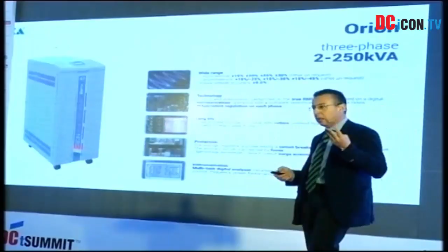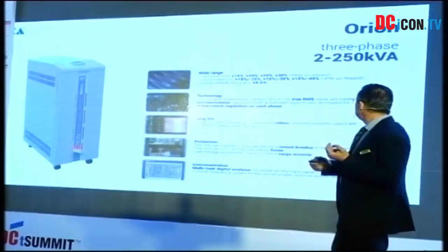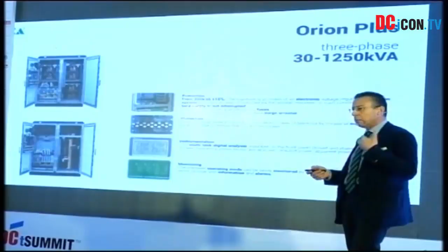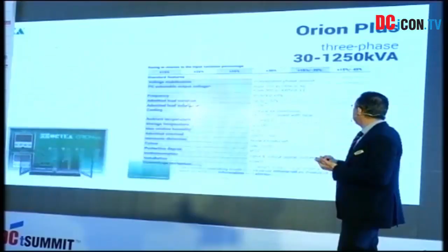And till 250 kVA, the units are based on 3 times the single phase. Starting from the Orion Plus model that reaches 1250 kVA, we start to have 3-phase mentality. So the unit will be equipped with electronic components and the electronic card that is able to manage 3-phase system directly. So after we have all these features, you can see that the panel boards are completely different and they are offering more features and more information. We can go to the Sirius, which is the only unit that can give you 6000 kVA.